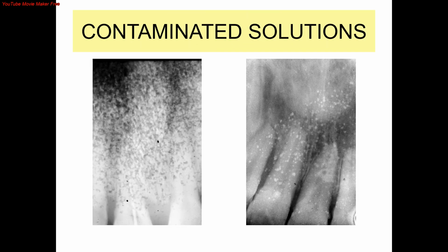Many times, this type of black and white spots are seen due to contaminated solutions or improper washing of the film. In such cases, you have to change the processing solution and repeat such radiographs.